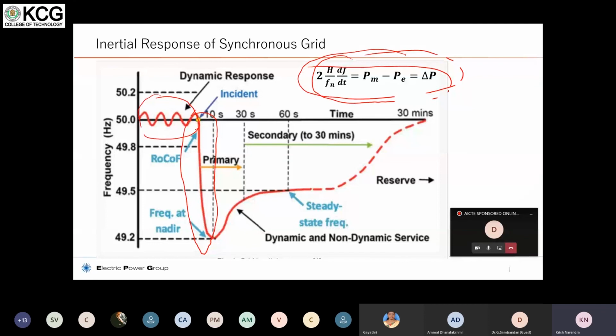When the frequency drops to an extent depending on the inertia of the system, inertial support comes in first. Later on, by using the frequency controls, the load shedding scheme and so on, you recover the frequencies area-wise, which takes anywhere from minutes to hours in the system. Later on, spinning reserves also come into the picture, depending on what the operators want to do to bring the frequency back to 50 hertz or 60 hertz.